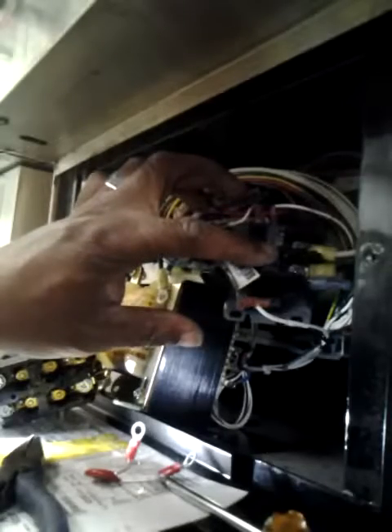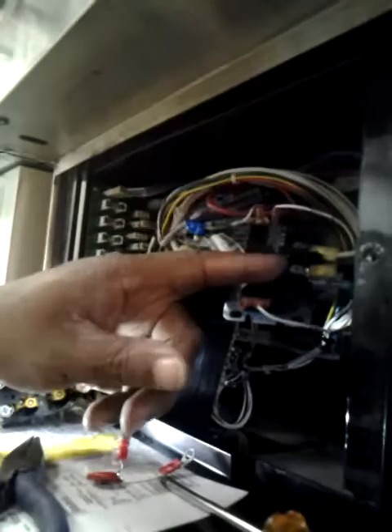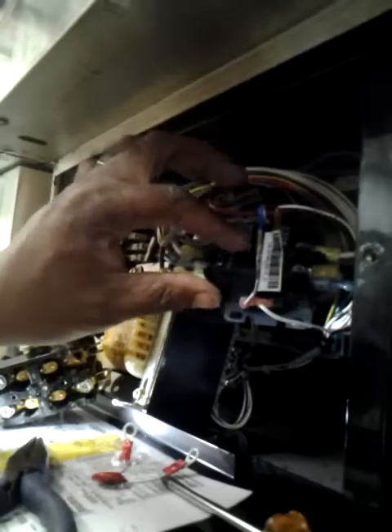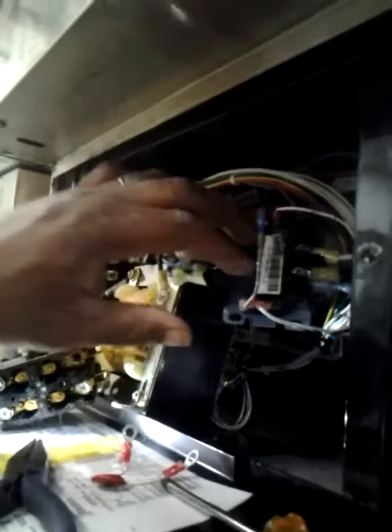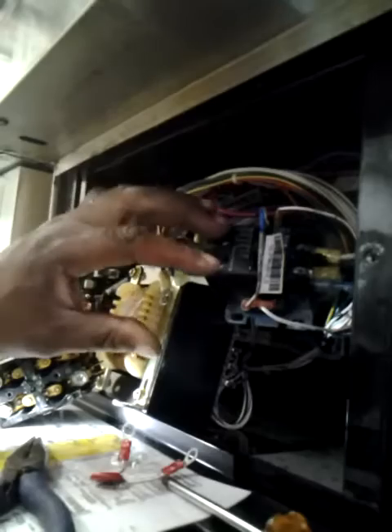This is on the transformer side, and this is the load side. This is where the power is coming from, and it's coming from here. So once I get this installed, I'll be able to test with my meter, test power right here, and I should be getting 200 to 220 volts. And then that causes this 24 volt coil, which is right in the middle here, to pull in and starts up the compressor. So when these pull in, you'll see it'll start up the compressor, and then power will flow through the contactor to all the other components through the outlet side.